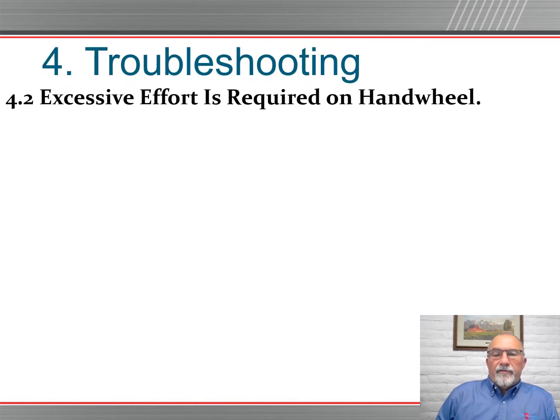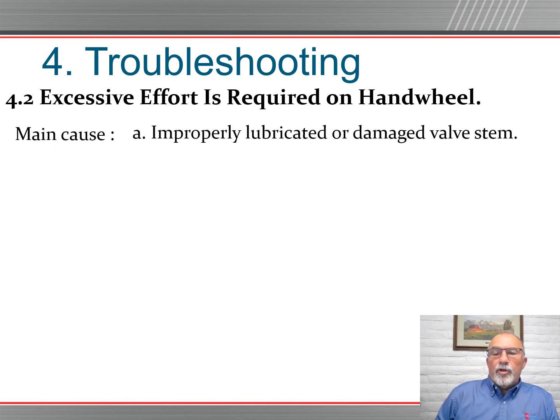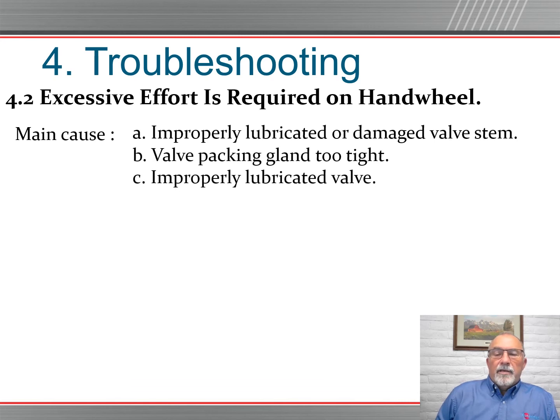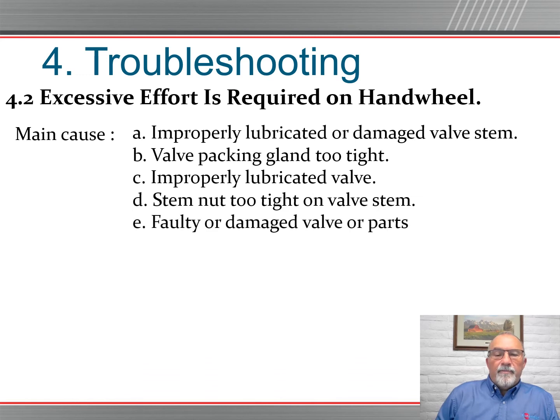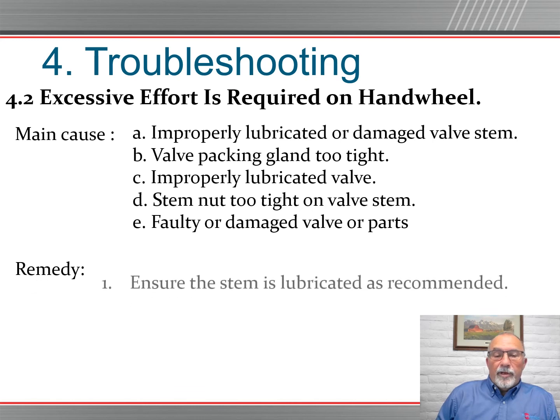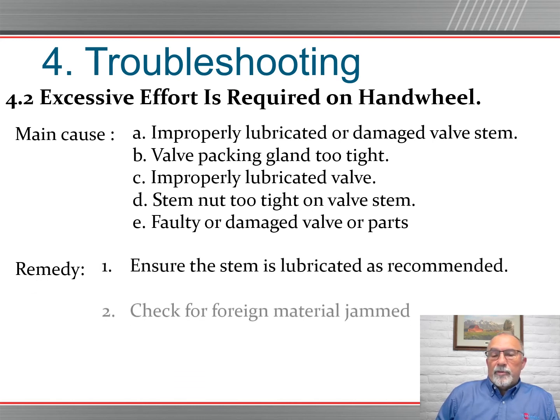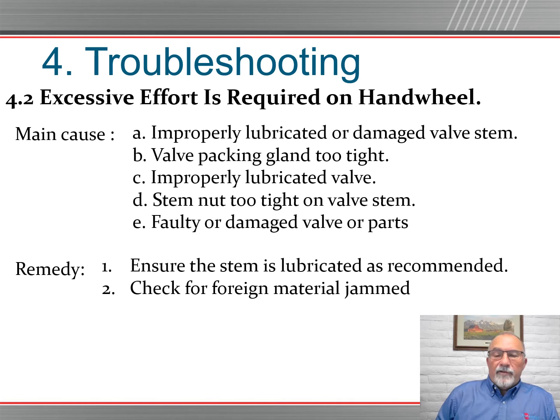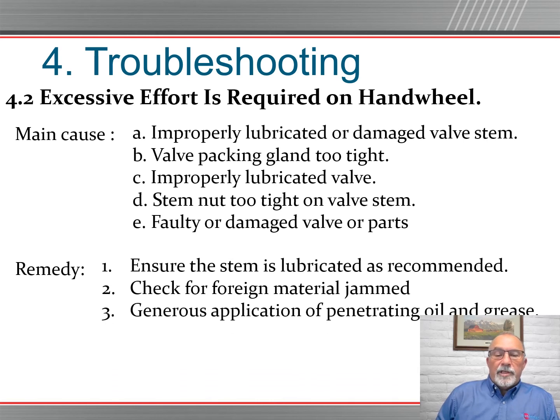More troubleshooting. Excessive effort is required on the handwheel. The main cause of this is improperly lubricated or damaged valve stems, a valve packing gland that is too tight, a stem nut that is too tight on the valve stem, or faulty or damaged valve parts. The remedy for these can include ensuring the stem is lubricated as recommended, checking for foreign material jammed in the seat, a generous application of penetrating oil or grease, or contacting Waterman valve for replacement.